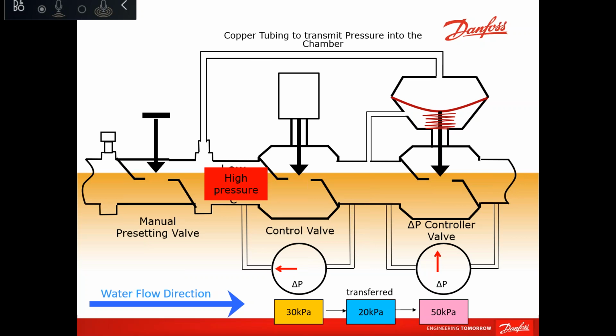If you are using PICV, do we still need to install a three-way valve on the fresh air handling unit? What we say is, we should not install a three-way valve if you are using PICV. Because, as we said, most of the time the system is running at part load condition. In the case of a three-way valve, when it achieves the load, it will bypass the flow. When you bypass the flow, you will reduce the return chilled water temperature, and we are back to that chiller case. Your return temperature will drop and you will consume more. Higher flow, low return equals more consumption.